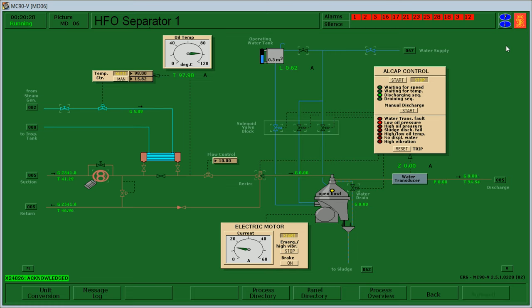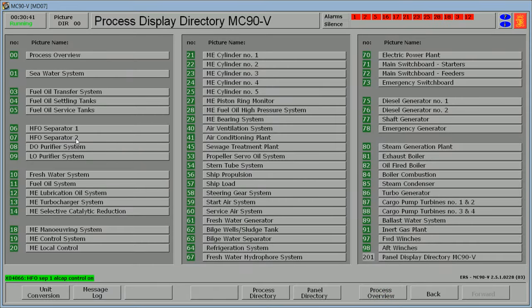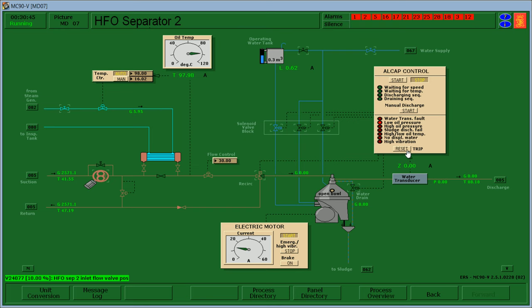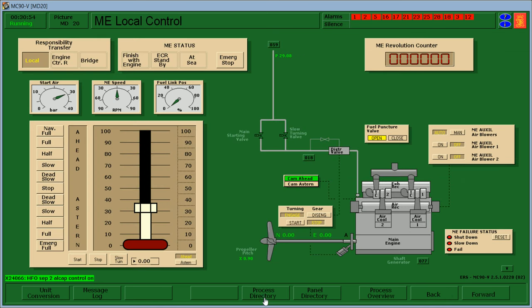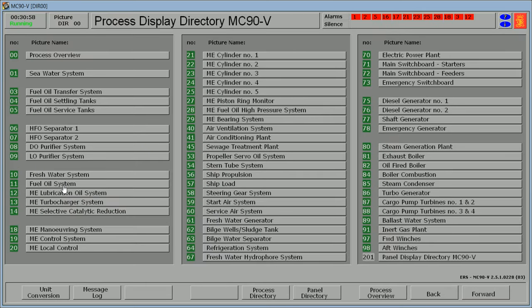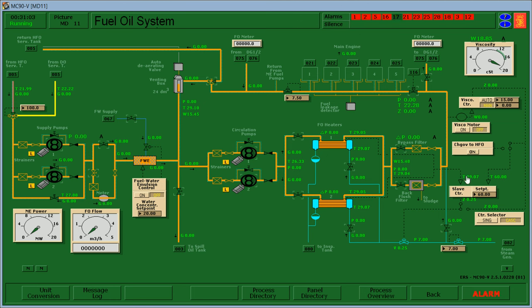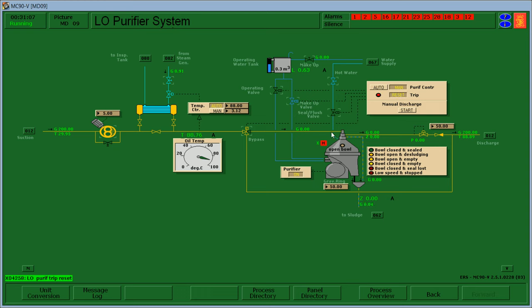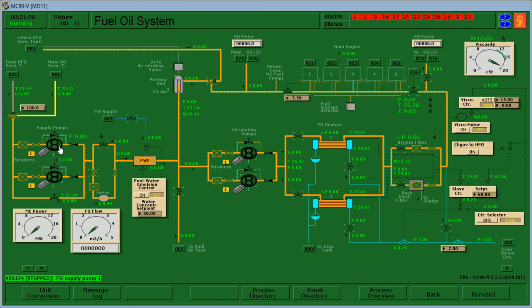The alarm is tripped. Low oil pressure. So we'll make the oil flow to 30. Start. Set. So we'll conduct trial and error here. Fuel oil system. Okay, reset. Set it to auto. Low at 10. So activate one of the supply pumps. But first, we open first the valves. Backflush or the bypass. Okay, the bypass here.